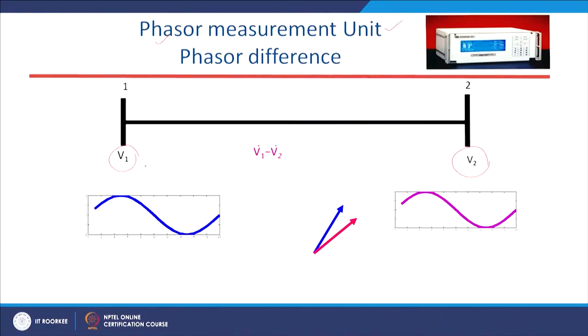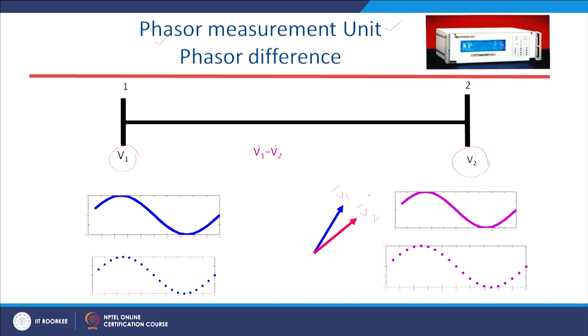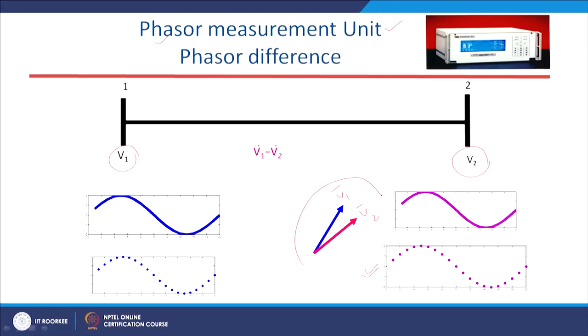The blue phasor represents V1 — the phasor position of bus 1 voltage — and the red one represents V2, the phasor position of bus 2 voltage. With advances in computing and signal processing, we are able to estimate phasors of voltage and current in real time. The DFT (discrete Fourier transform) algorithm runs inside the PMU to estimate voltage and current phasors for further analysis.